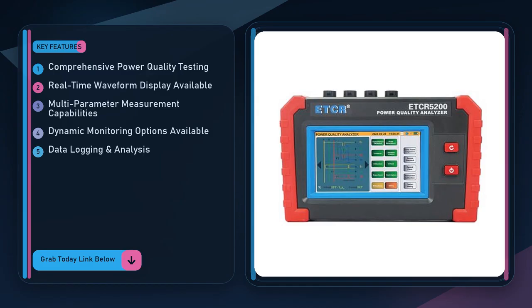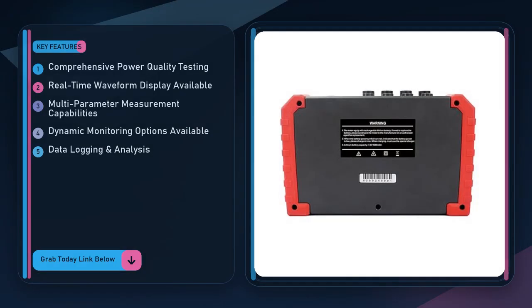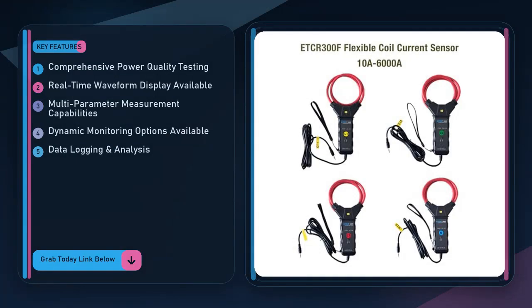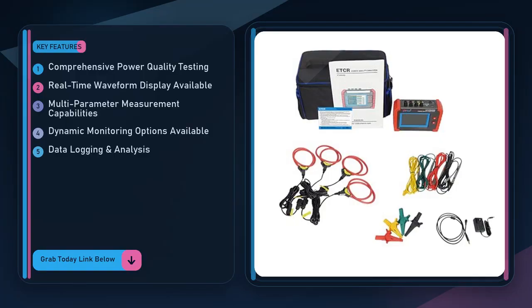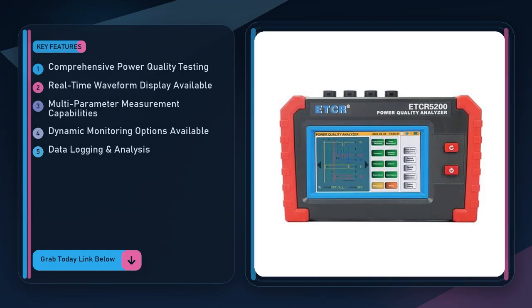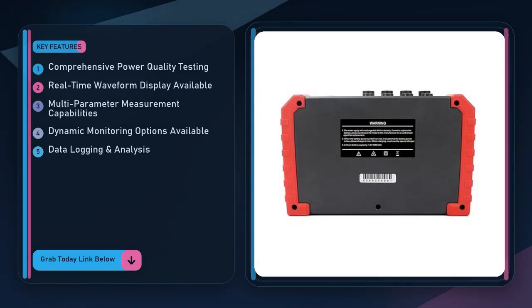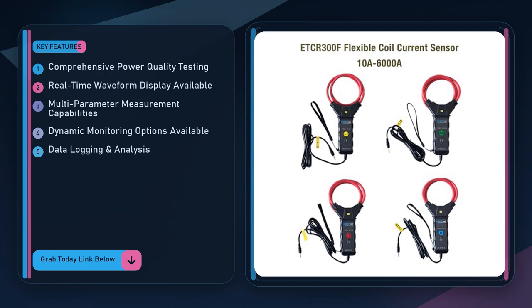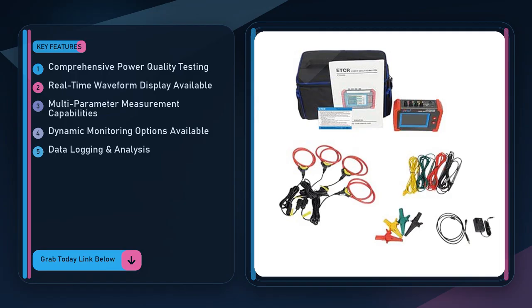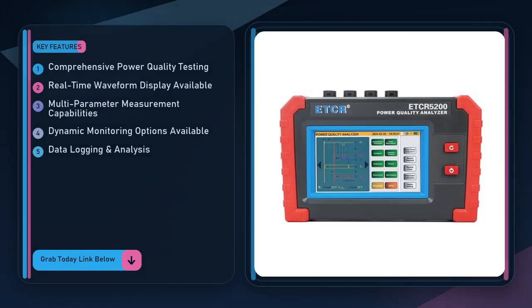One of the biggest strengths of the ETCR5200 is its multi-parameter measurement capability. It captures voltage, current, frequency, power factor, total harmonic distortion, and a handful of other metrics simultaneously. In a typical day, I've seen users connect the clamp to a motor feed while the analyzer logs data for a full 24-hour period. When the logs are downloaded later, the trend analysis feature highlights exactly when the voltage dip occurred, how long it lasted, and how much the harmonic content spiked. That kind of historical insight is hard to get from a basic handheld that only shows instantaneous values.